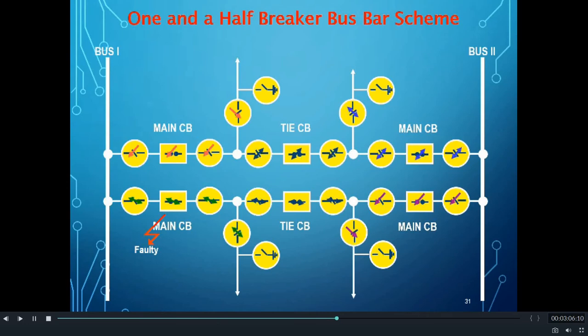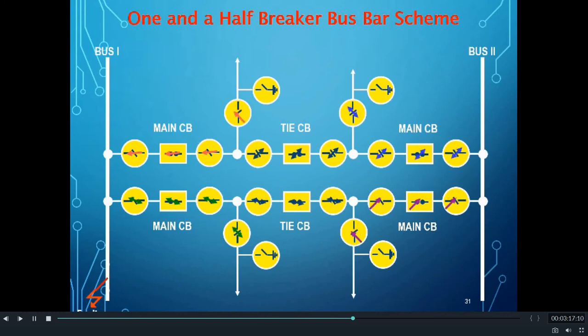Now let us see what happens in case of a bus fault. There is a fault in bus one, so the circuit breakers connected to bus one — the main CBs of two of the feeders — will trip. Because of the opening of these two main CBs, the faulty bus one gets disconnected from the system.